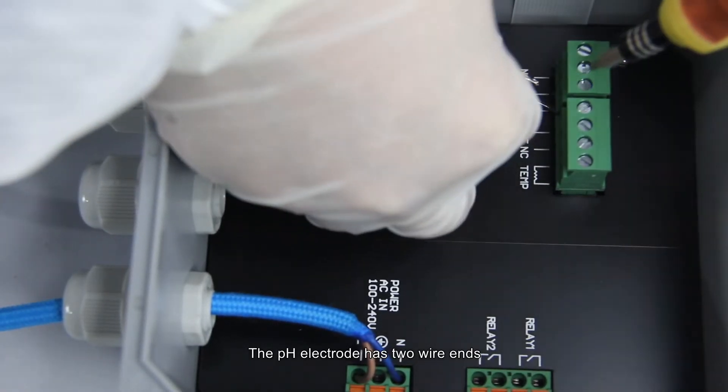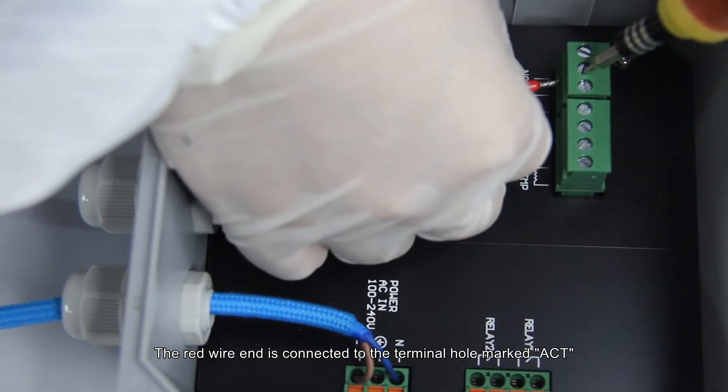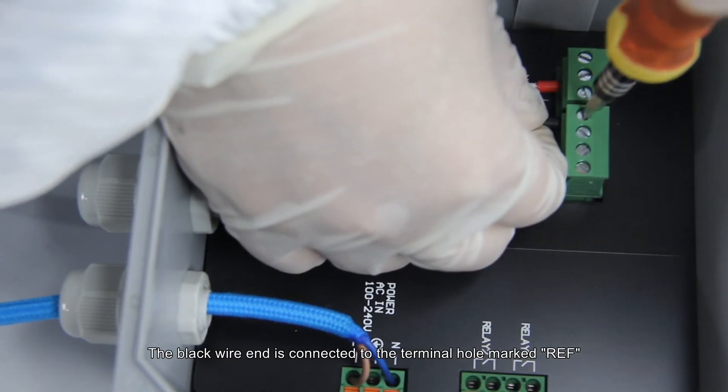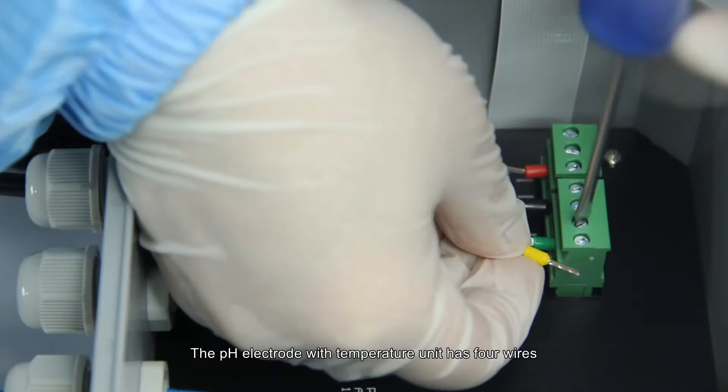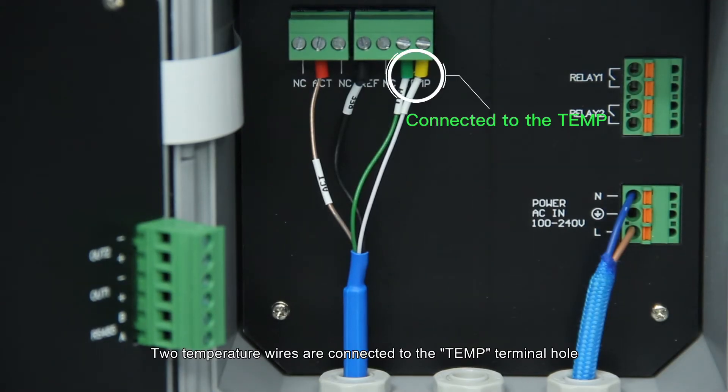The pH electrode has two wire ends. The red wire end is connected to the terminal hole marked ACT. The black wire end is connected to the terminal hole marked REF. The pH electrode with temperature unit has four wires. Two temperature wires are connected to the temp terminal hole.